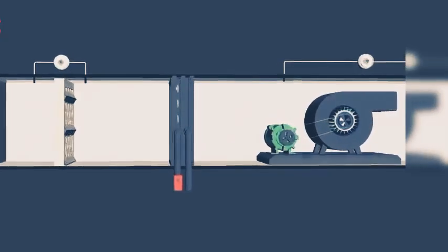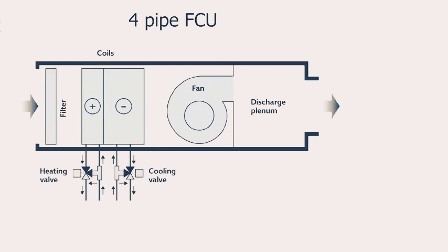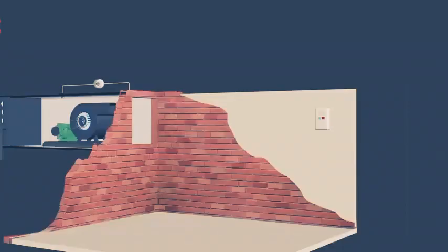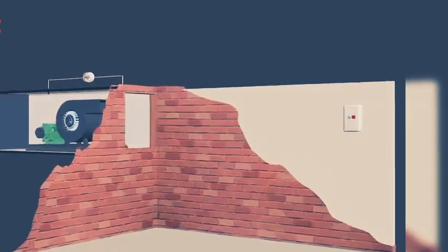2-pipe fan coil units, as in our case here, have one supply and one return pipe. The supply pipe supplies either cold or hot water to the unit depending on the time of year. 4-pipe fan coil units have two supply pipes and two return pipes. This allows either hot or cold water to enter the unit at any given time. So, let us see the working principle of fan coil units.